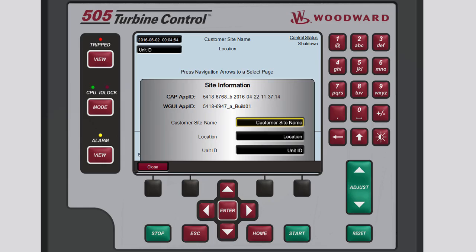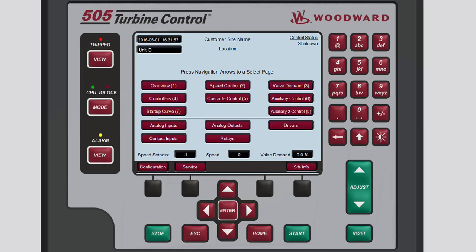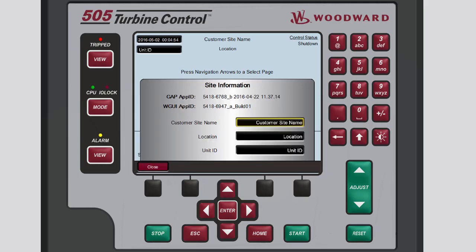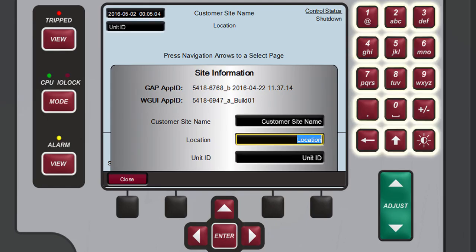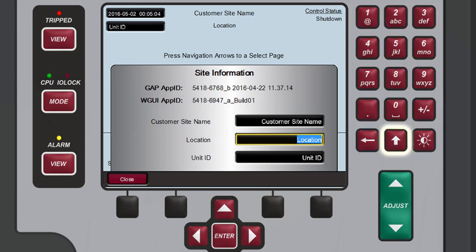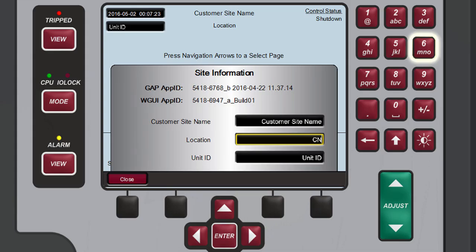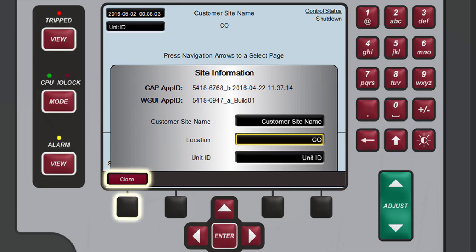The last thing we'll cover in this tutorial is how to access the Site Information screen, which displays your site's name, location, and unit ID. From the Home screen, press the black Function key below Site Info. To change the value in any of the text boxes, use the navigation crosskeys to highlight the applicable box. Press Enter to select the value currently displayed in that box, then use the numeric keypad to enter the new value. To capitalize letters, first press and release the Shift key, then press and, if applicable, hold the desired number key for the desired letter. Note that because the numeric keys also contain letters, you will have to press and hold a key if the initial character is not the one you need. Holding the key allows the unit to cycle through the available characters for that key. Stop pressing the key to select the desired character. Press Enter to accept the new value. To close this Site Information pop-up window, press the black Function key below Close.